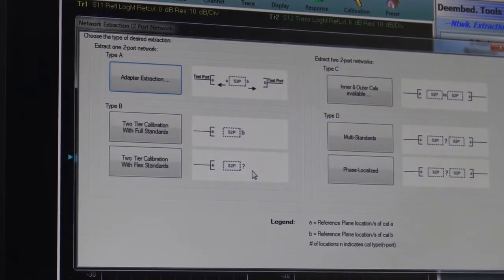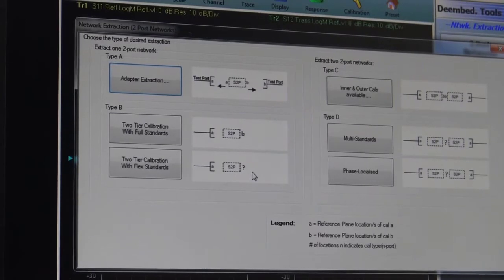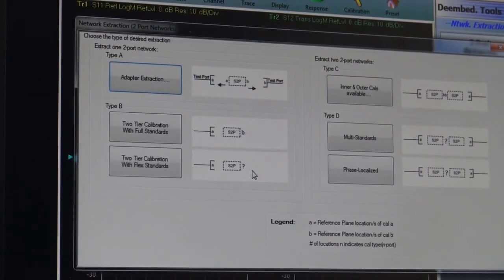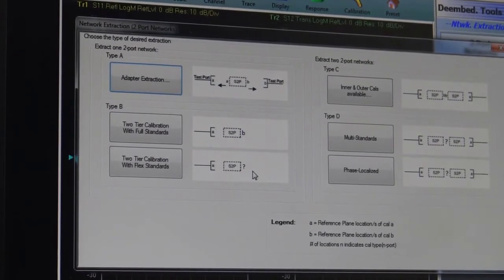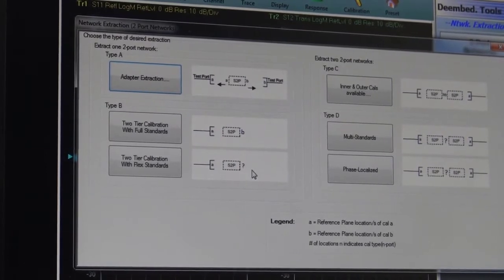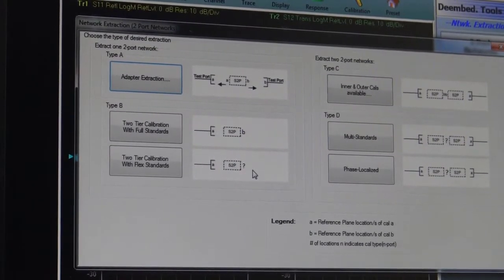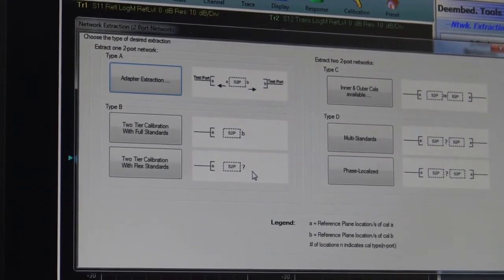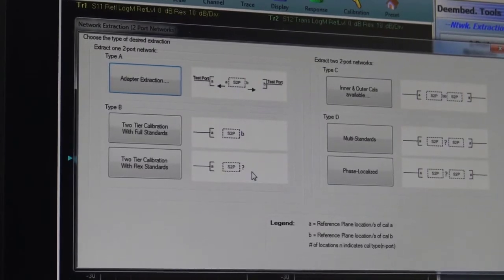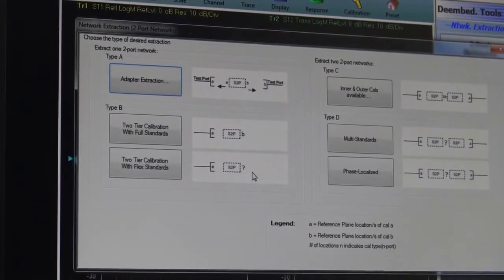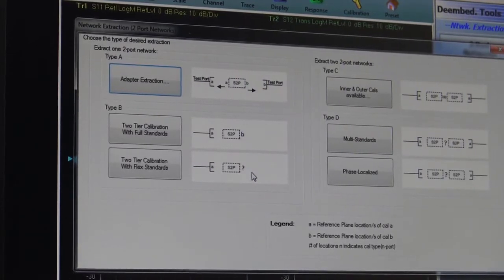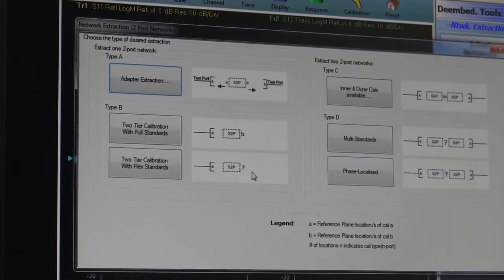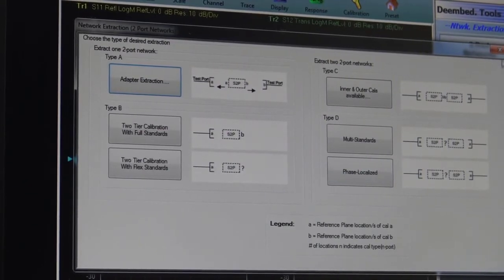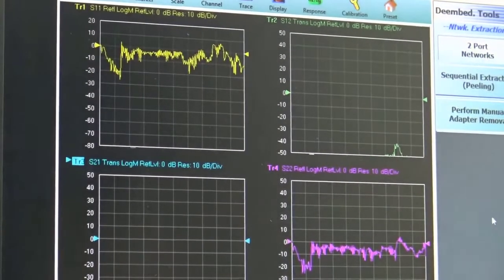So the universal fixture extraction option will help you out in that whatever you have in terms of information on a standard, say a short for instance, if that's all you have, then you can input that in, and an S2P file will be generated, taking on other certain assumptions in the calibration in order to incorporate that short information into your S2P de-embedding network. So in any case, if you have those types of things that you want to set up, this is where you would do it in the calibration.